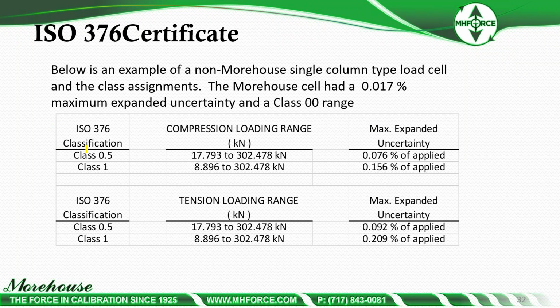Trying to explain with that range there, the classification and some of the other stuff that's going on. So class half in this situation was 17.793 to 302.478 kilonewtons with a max expanded uncertainty 0.076. But if you look at class 1, the class 1 loading range is greater. This instrument can be used at lower capacities if they meet class 1, and at higher capacities for class half.